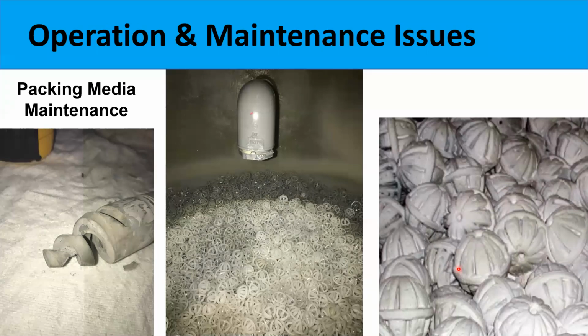And the worse off they get, the harder it is to remove any kind of contaminant that's built up on these. Sometimes you can perform an acid wash or some type of internal wash of the system, but sometimes you just have to completely replace the packing media. And if these systems are operated properly, the packing media can last 20 or more years without having to be replaced. If they're not operated properly, it may be a year or two where you need to replace the media in the system.